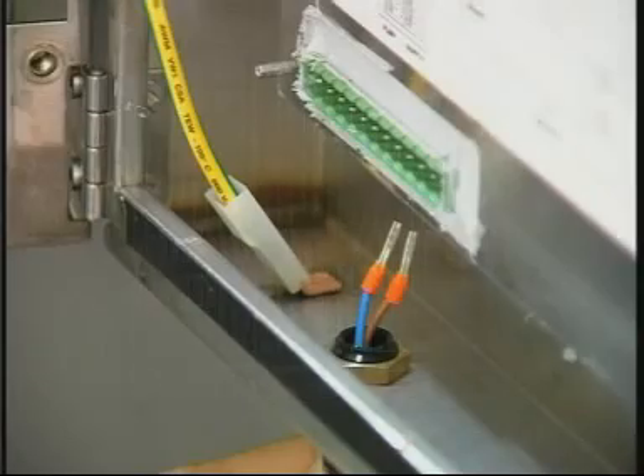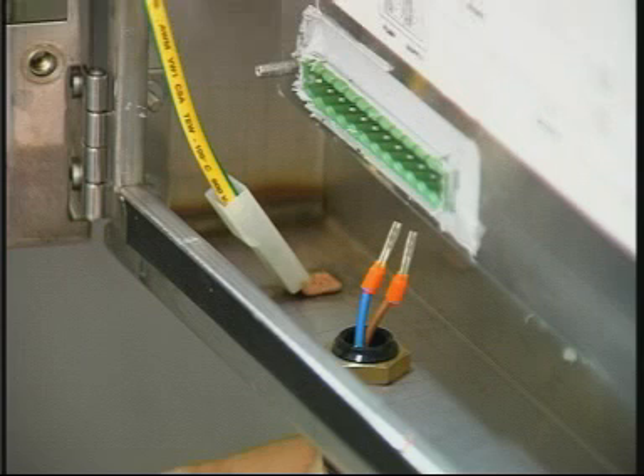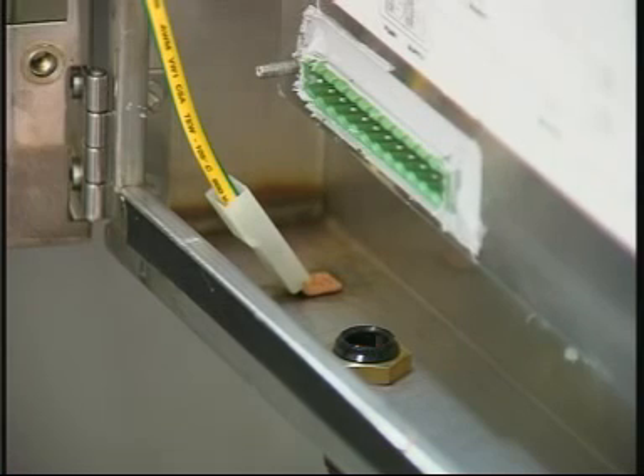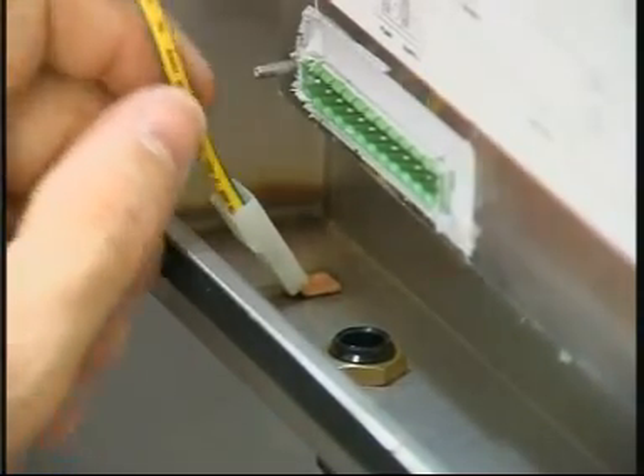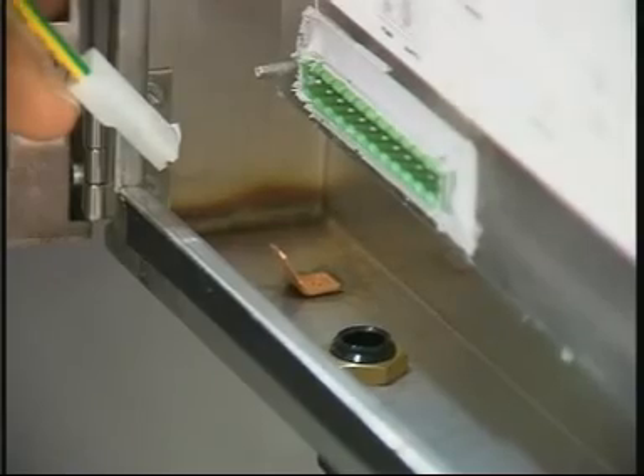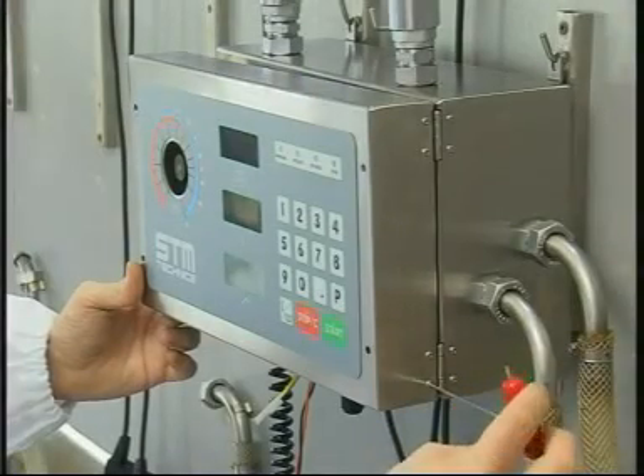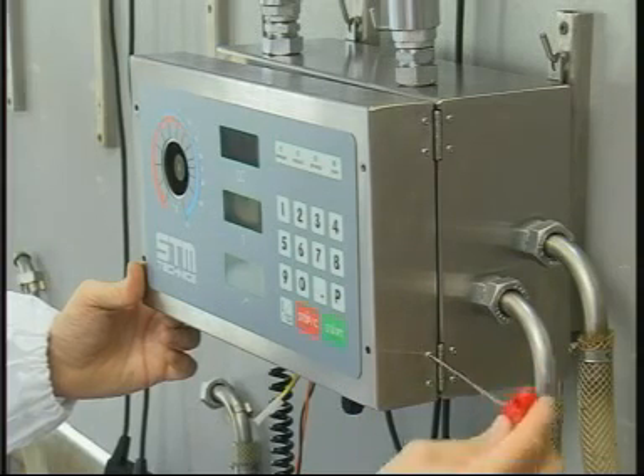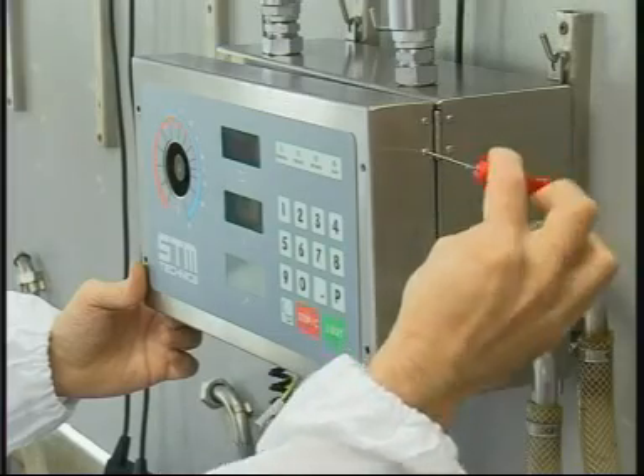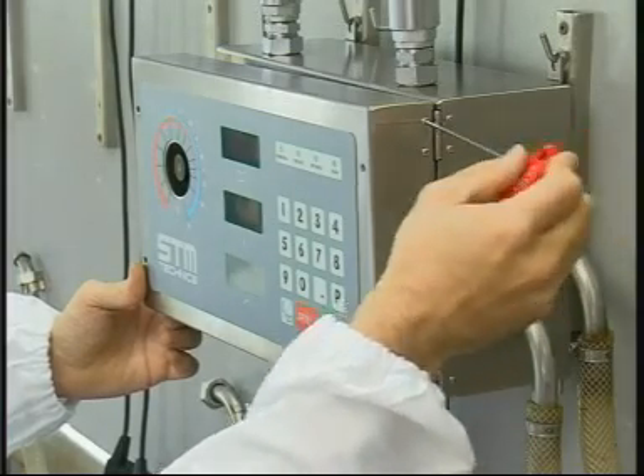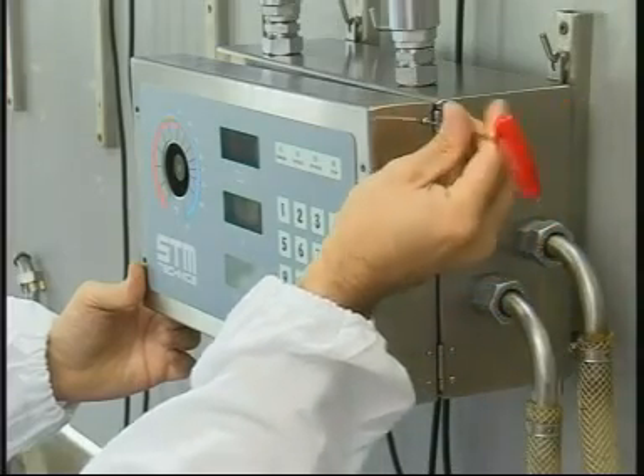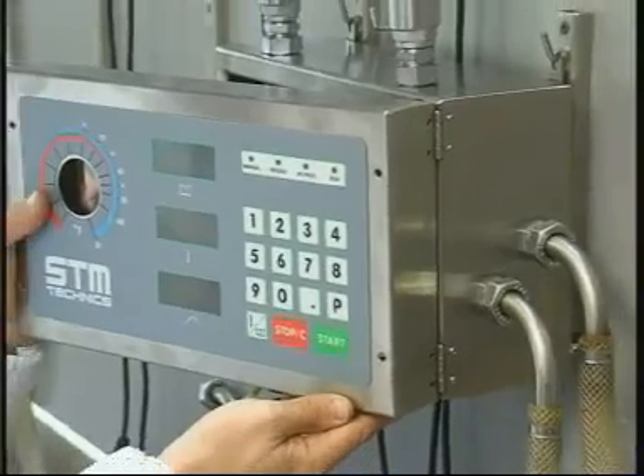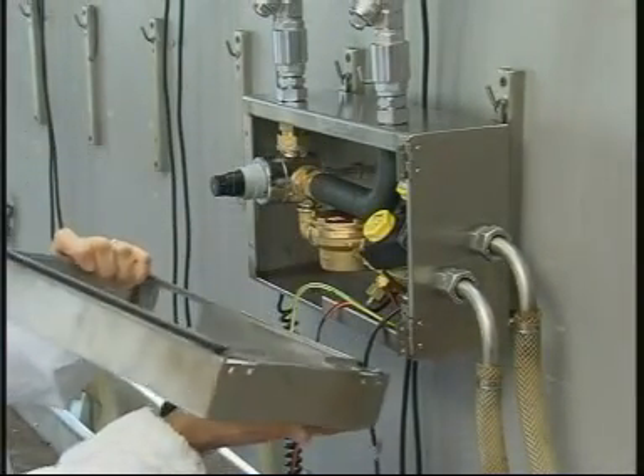Cover disassembly. If the faults cannot be identified on the parts hitherto analysed, for example, the machine doesn't switch on despite the fact that the fuses and the power board have been replaced, or if some segment on the displays doesn't turn on, or if there continue to be failures with a probe despite the fact that they have been replaced, this means that the whole cover must be replaced. With the power board disassembled, remove the external probe. Disconnect the earth wire. Unscrew the fastening screws from the hinges and remove the cover.